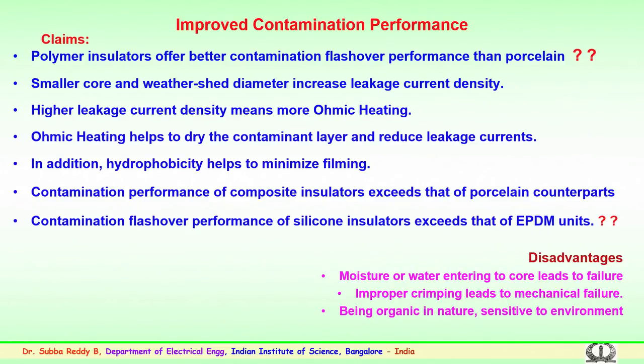As mentioned, the contamination performance of the composite insulator exceeds that of the porcelain. This has been noticed in the field, in the literature and in field condition reports: particularly for contamination or pollution, polymeric insulators offer better performance in comparison to the earlier ceramic or porcelain insulators. The contamination performance of silicone or composite also exceeds the EPDM units, which were the earlier version of silicone rubber. So, much better in case of pollution or contamination.